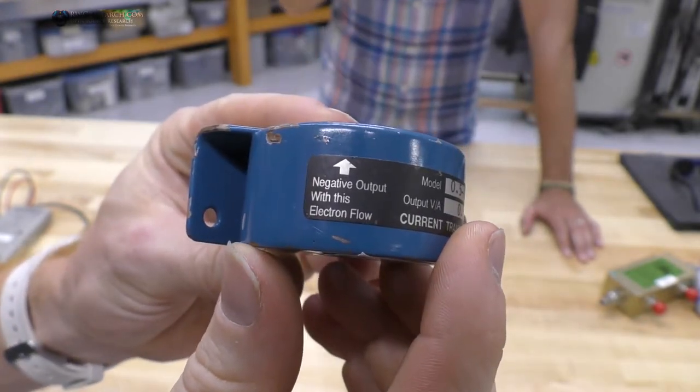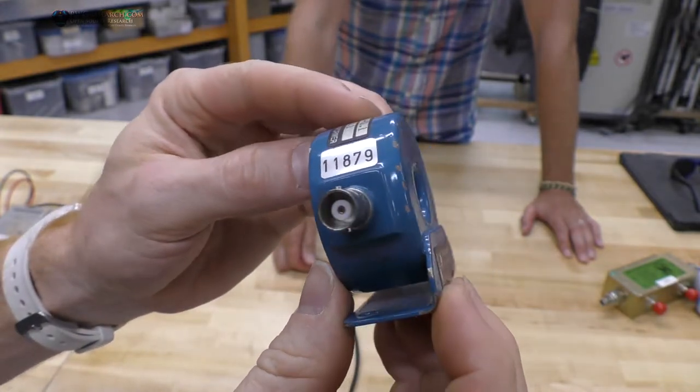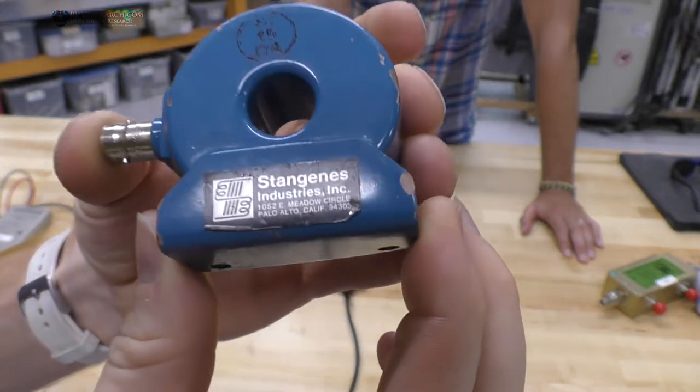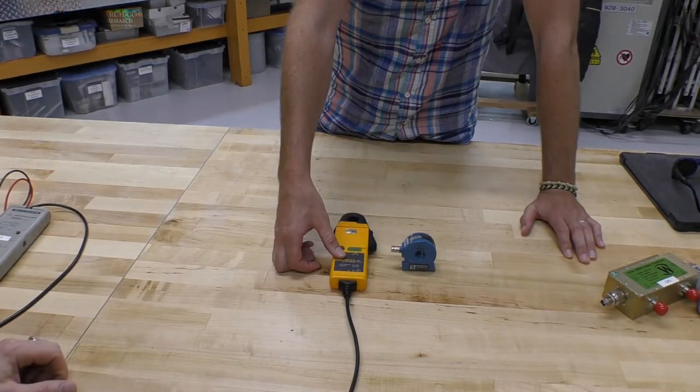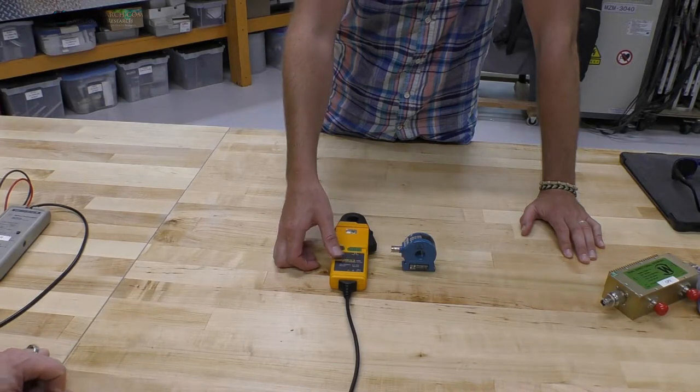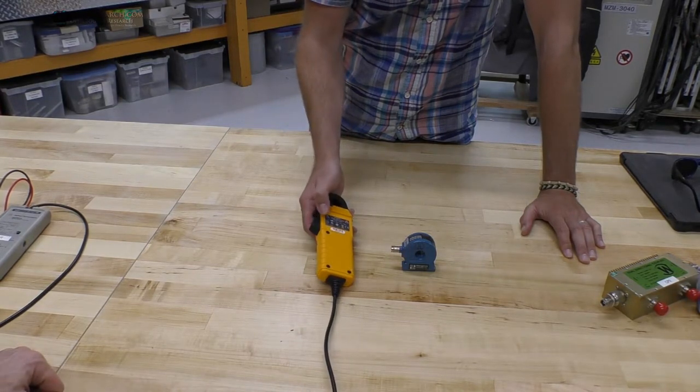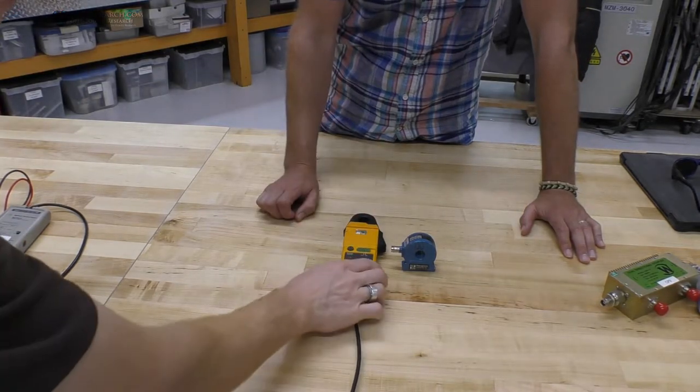So a more cost-effective probe is the Fluke unit, this is the Fluke I30S, and this will do up to 20 amps RMS, so 10 to 1 probe, and I think the frequency is up to about 10 kilohertz or so.